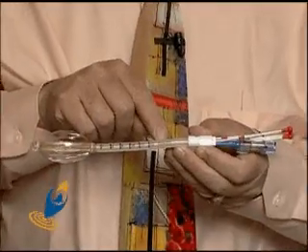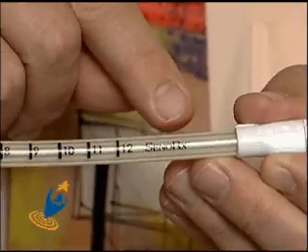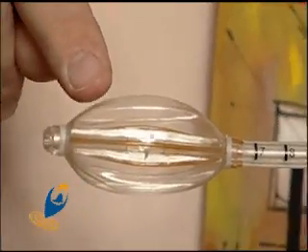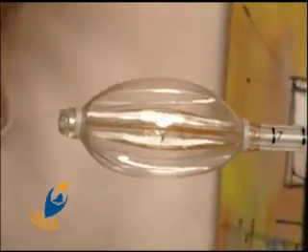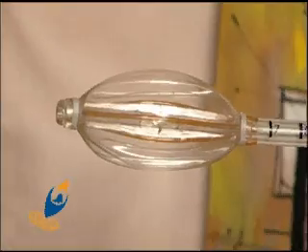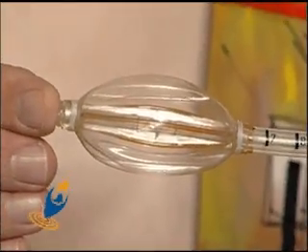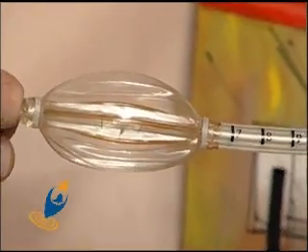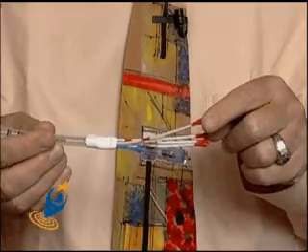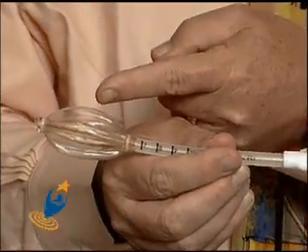The next device is from a company called Cianna Medical and it's called the Contura — C-O-N-T-U-R-A. It has similarities to the other balloon catheters but the yellow offset catheters are a little more separated from the central shaft than in the MammoSite ML, giving me even more ability to pull dose away from the skin and off the ribs. You have the simplicity of a single entry intracavitary device. The radiation enters through these shafts with that same robot sending a radioactive source inside the balloon, which would be inside your breast.